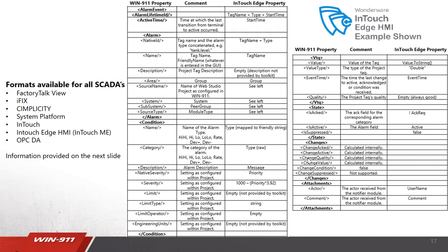So formats are available for all SCADAs. I will say that in our canned formats, we have generally provided short and verbose variations, as well as what we call condition variations. Some SCADA packages really emphasize the alarm condition, others really emphasize the alarm point. And so often it's a good idea to switch over to the condition formats, short condition, long condition type formats, if you're dealing with a SCADA package that really emphasizes the condition.